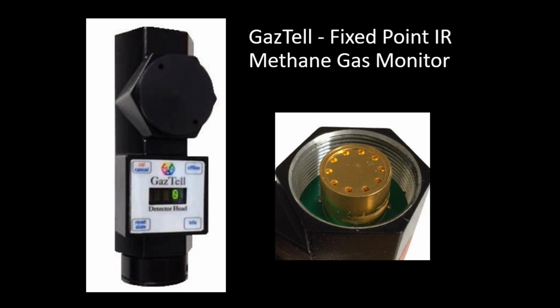The fixed point IR is an infrared detector that uses optics to actually sense the presence of gas. And it's very simple. We're not going to go over the fundamentals. We did that in an earlier webinar. But basically what it does is it has a light source and a detector at a specific wavelength. And when gas comes in between the light and the detector, it absorbs the energy produced by a specific wavelength of light, and therefore the detector sees less of a signal than if it was just clean air. And of course, with electronics and algorithms and software, we can determine what the concentration of the gas is just by the amount of light that's absorbed.